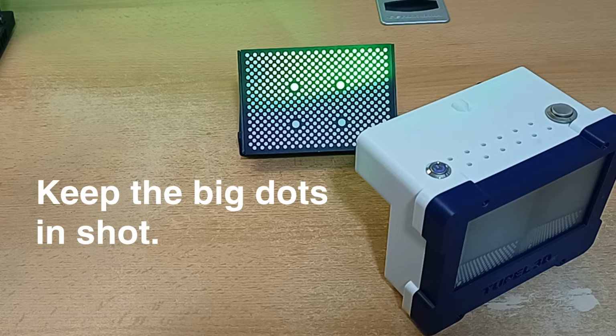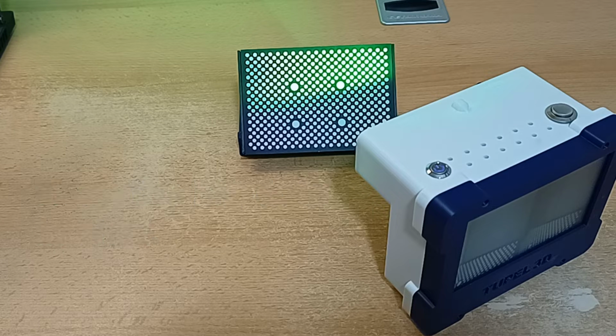If you're wondering why it needs to be calibrated, it could be that the temperature changed since the last time it was calibrated, and to get down to 10 micron accuracy levels, even the slightest thermal expansion of the machine has to be accounted for. Be careful with your calibration plate, because it's quite easy to scratch, and this could reduce the accuracy of the scanner. However, the holder keeps it safe.